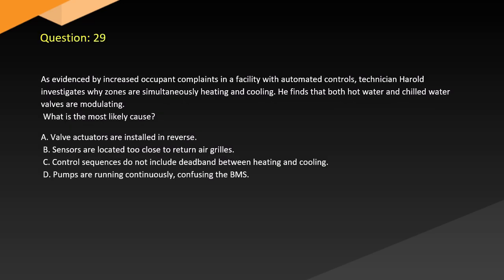Question 29. As evidenced by increased occupant complaints in a facility with automated controls, technician Harold investigates why zones are simultaneously heating and cooling. He finds that both hot water and chilled water valves are modulating. What is the most likely cause? A. Valve actuators are installed in reverse. B. Sensors are located too close to return air grills. C. Control sequences do not include deadband between heating and cooling. D. Pumps are running continuously, confusing the BMS.